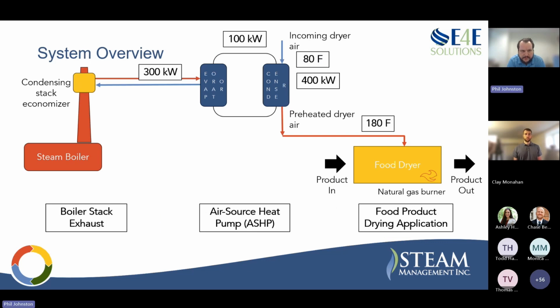So in this example, we take an economizer, take that energy from the boiler stack and transfer that heat to an incoming process. This is air, so we're not using water anymore. This is actually air source, and we're driving that heat into a makeup air for a food dryer.